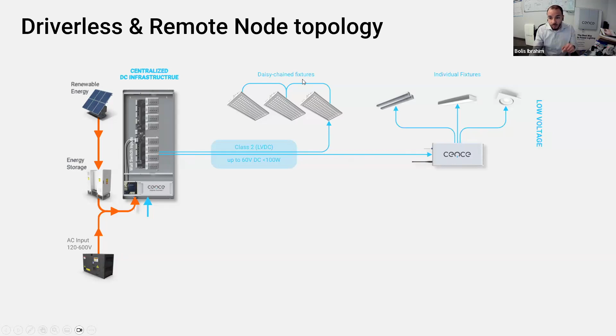Driverless LED fixtures are a great example of this bus approach. The benefit is you centralize all your intelligence or driving capability into the cabinet, or a PoE switch - we'll talk about PoE lighting too. These fixtures are hot swappable, located in a single cabinet, and give higher lumen per watt efficacy since there's no driver on the fixture, so your lumens per watt go up.